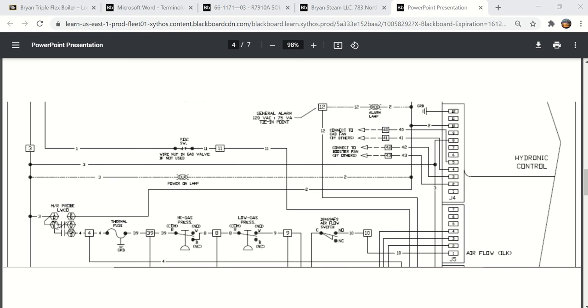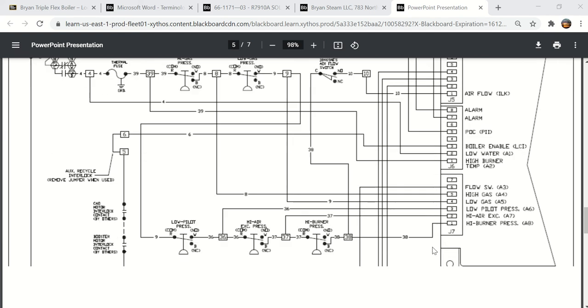And the reason that it's shown as the alarm is the normal position is because if there's no water, that is the normal position. Once it detects water, it will open this contact and close this contact. Then when it closes this contact, you get power through here to terminal number 4. And we'll look at the 2 points that terminal number 4 goes to. One is to the thermal fuse here, but it also goes down here, and I'm going to have to scroll down to the next page, and you'll see where it comes down from 4, and it comes down to this terminal J62, which is called low water A1.